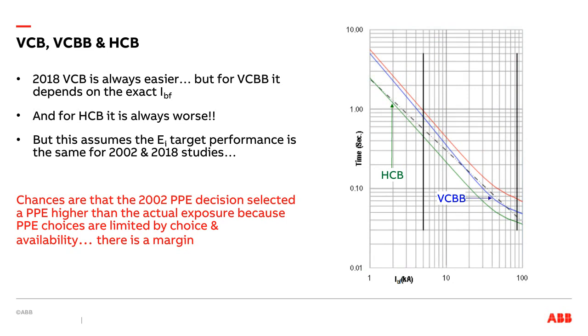Most people, when they select PPE, will select PPE that is higher than the actual calculated values. Most users will have PPE policies that are either 8, 25, 40, or some calorie value. They don't have 40 different levels of PPE in their facility. They will typically have 2 or 3, and typically they'll choose those values that were previously associated with hazard risk categories, or may have some other value. Whatever it is, that facility has a value of PPE that is used, typically 2, a low and a high, and that is what is used.